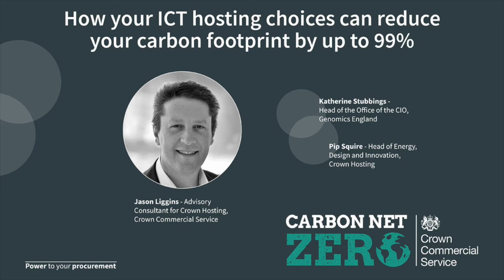I think the most exciting place that we're working at the moment is how we use our battery storage systems, because clearly to have a guaranteed power supply, we have a lot of battery storage to be able to bridge over the time between power going off and generators coming on. Now, if we can harness that battery power and make our energy centers work like a peak lopping power station, that will provide to the local distribution network added resilience and added stability, which will encourage more renewables, which are typically intermittent, onto the grid without having to spend a huge amount of money on the grid itself by government and people and the taxpayers to create that stable grid environment to keep the power on. And to do that, I think, is a really good social bit of engineering that comes out of the infrastructure that we have to have and making it work not just for the data center, but for everybody in our neighborhood.